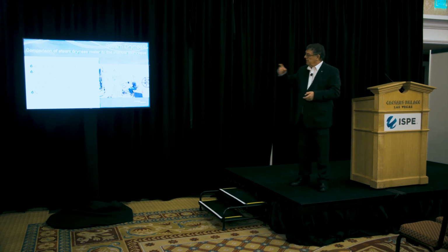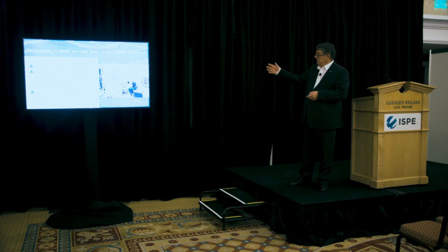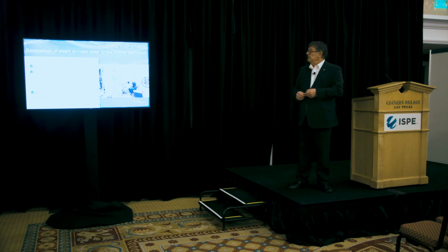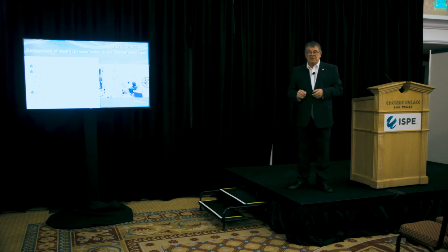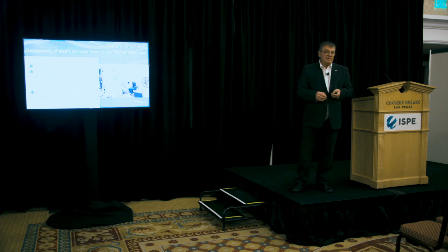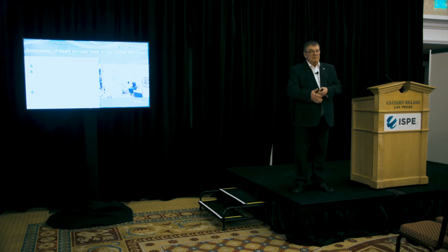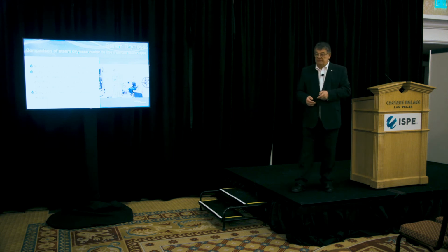So this is a picture of our test line in Cheltenham, where we have the Spirax Sarco Global Technology Centre. It's where my office is based. And you can see on that control panel just how much infrastructure we have in terms of control. The reason for that is, how do you create steam at a known, guaranteed dryness level? So we start with steam, we superheat it to a known value, and then we inject water and make sure the water's mixed. And we then know at a point in that line exactly what the dryness is. And that's what's been underpinning all of this work that I've been explaining today.